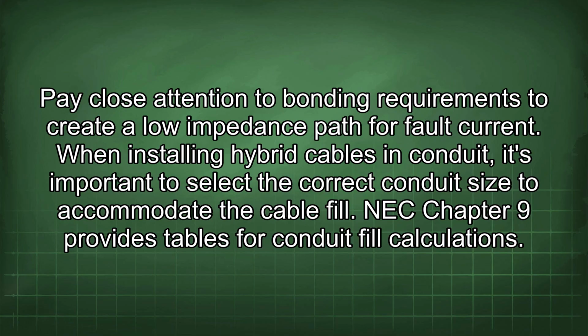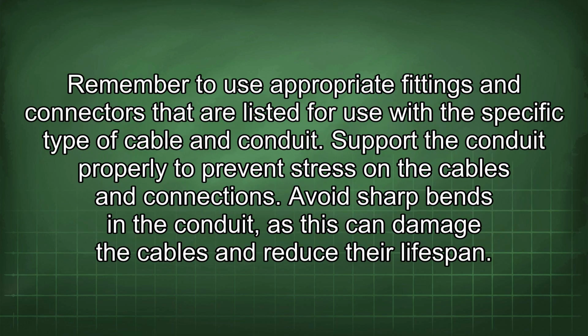When installing hybrid cables in conduit, it's important to select the correct conduit size to accommodate the cable fill. NEC Chapter 9 provides tables for conduit fill calculations. Remember to use appropriate fittings and connectors that are listed for use with a specific type of cable and conduit. Support the conduit properly to prevent stress on the cables and connections. Avoid sharp bends in the conduit, as this can damage the cables and reduce their lifespan.